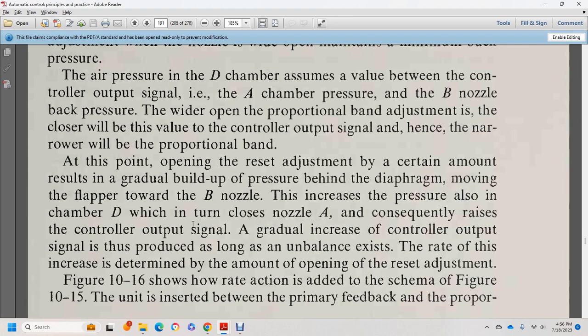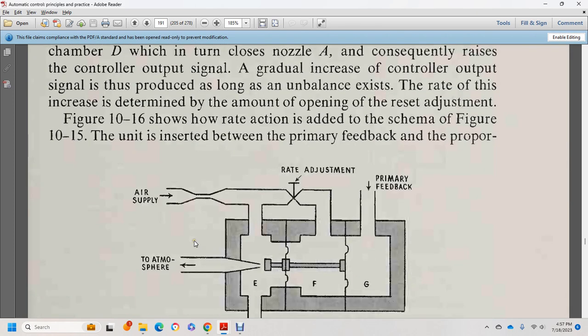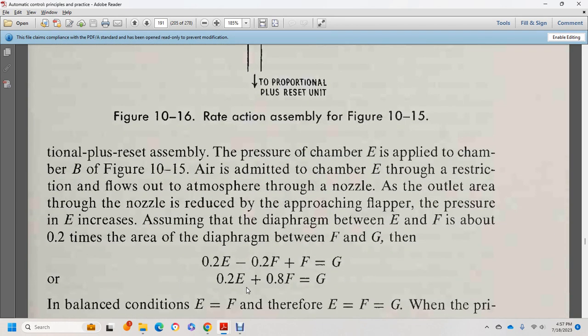With the reset adjustment, a gradual build-up of pressure behind the diaphragm moves the flapper toward the nozzle B, increasing pressure in chamber D, which causes the control output signal to gradually increase — this is the reset action. The rate of this increment is determined by the amount of opening of the reset adjustment. Figure 10-16 shows the rate action added to the schematic of figure 10-15, with the rate adjustment unit inserted in the primary feedback path.